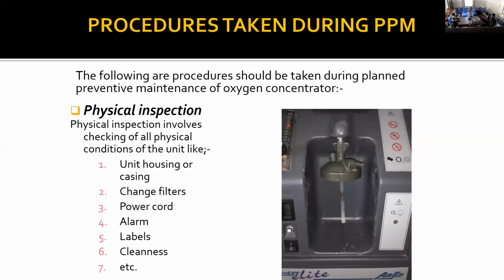Thank you. The following are the procedures to be taken during planned preventive maintenance of an oxygen concentrator. First of all, you have to do the physical inspection. Physical inspection involves checking the physical condition of the unit: first checking the unit housing or casing, changing filters, checking the power cord, alarm labels, cleanliness, and so on.